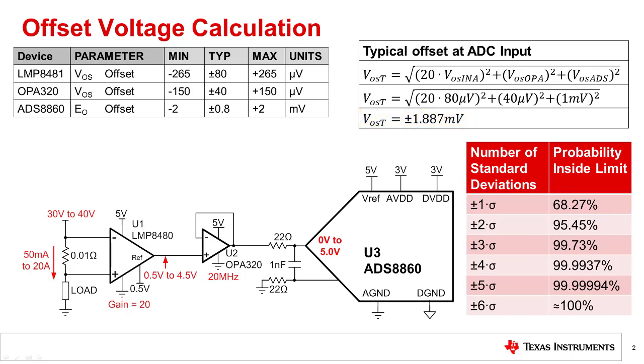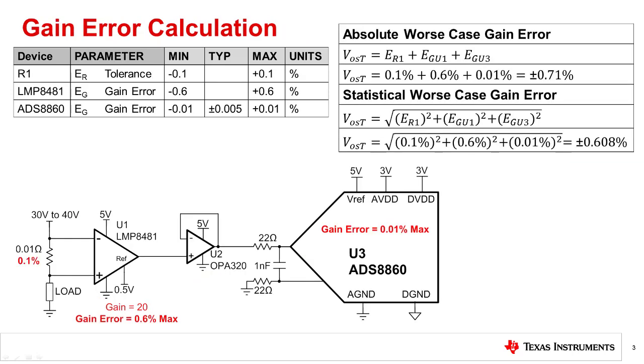To set a worst case limit, we can multiply the standard deviation by the appropriate factor from the table according to the system requirements. For example, if we set the system maximum specification to plus or minus three standard deviations, then 99.73% of the population will be inside that limit, and 0.27% of the population will fail the limit. Depending on the requirement, a more conservative limit can be set.